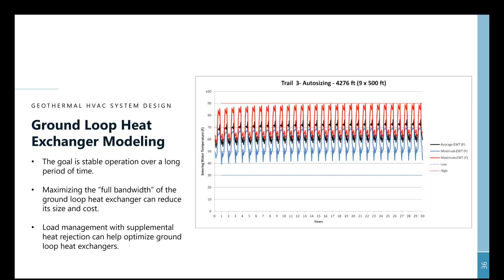So what are some options for this load management? Traditionally, you'd see an evaporative cooling tower used, similar to a traditional chiller system, rejecting heat to the environment. But again, we're trying to be more water conscious, not just energy conscious. Open loop cooling towers can use a considerable amount of water every year, so the industry has advanced with air source equipment like this air to water heat pump, which can optimize the bandwidth of your system and utilize the ground to its greatest effectiveness.